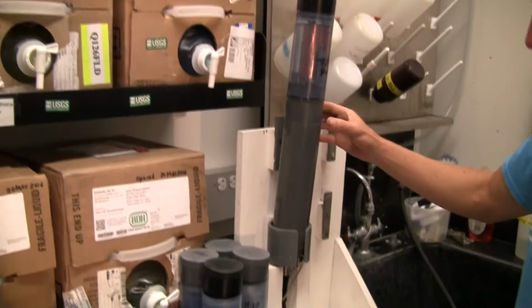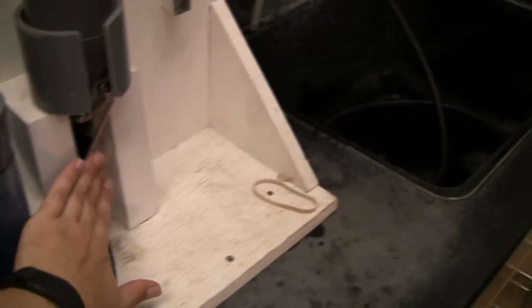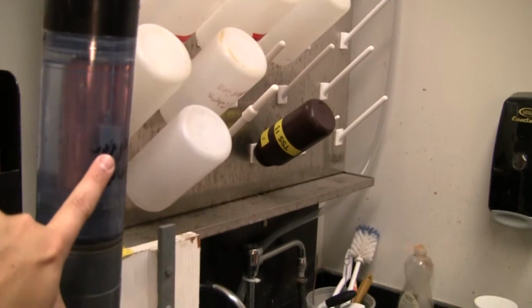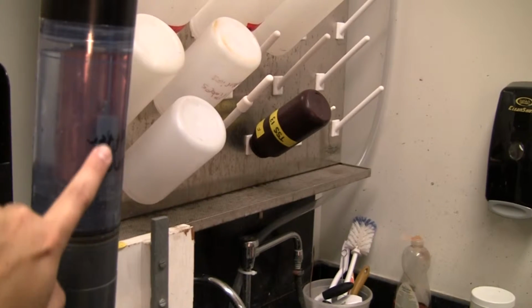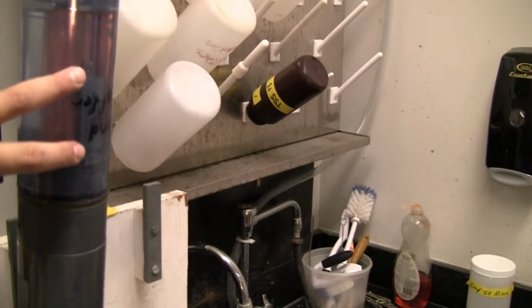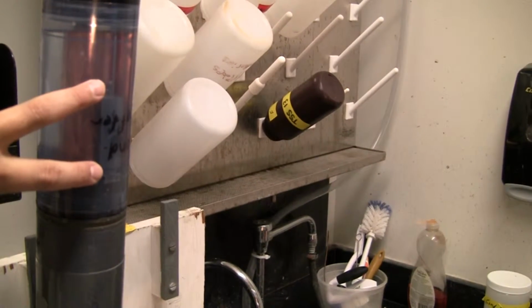And place the unit upside down into the Sonde holder. This is where the cable goes, so that way it's protected. And so the sensor is upside down in the solution so that all the solution will cover the entire sensor of the conductivity sensor, which is this little one right here.